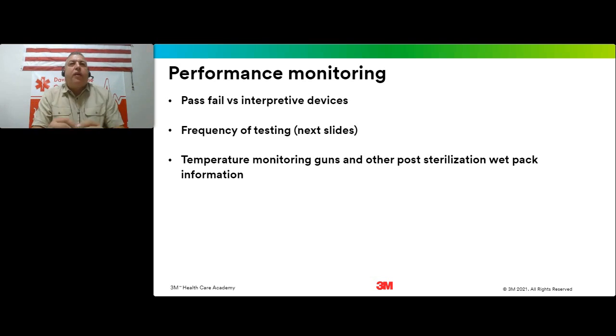You're all familiar usually with the moving front indicator. That's an indicator where a little pellet melts under certain conditions, and it moves forward to cross over a pass line, if you will. So those are a little more interpretive. They can tell you more of what's going on inside of a cycle. So it takes a little bit more to look at devices like that and interpret whether they've passed or failed. So it's very important that we know how to use those and are we using those.